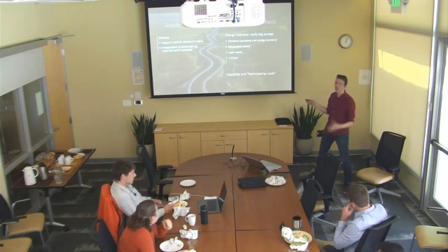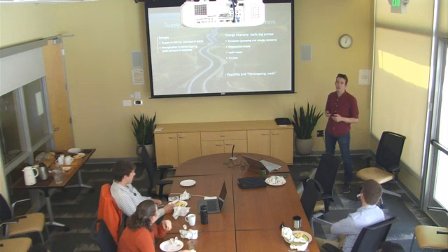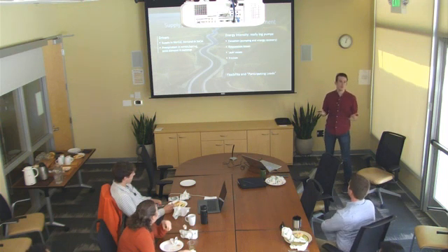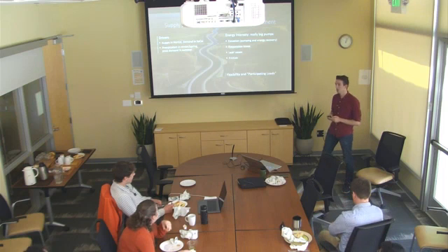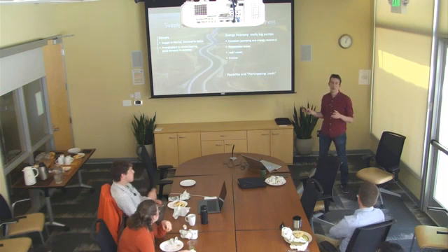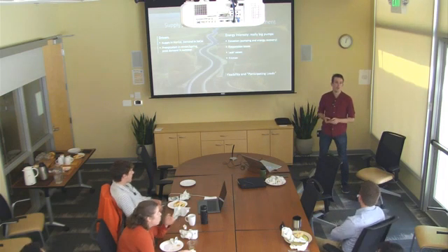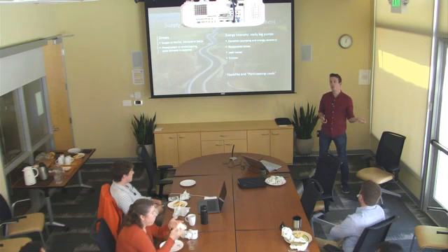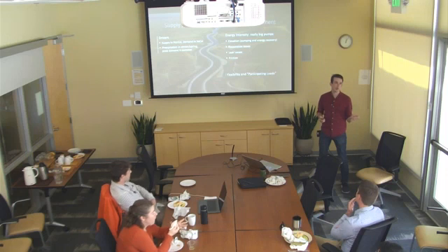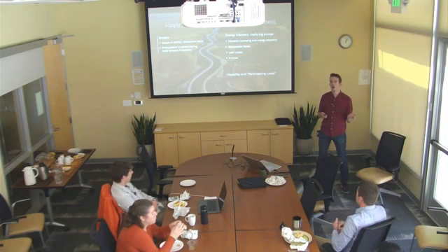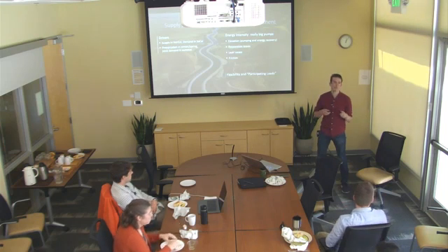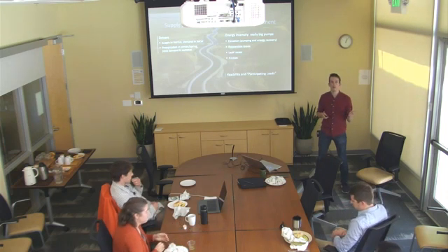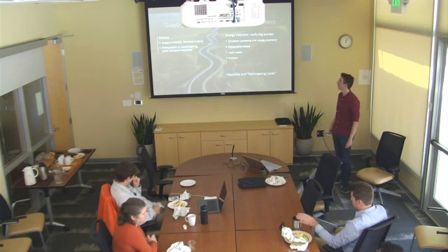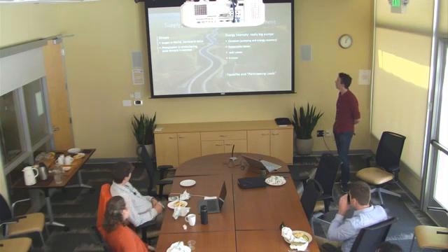One thing about the flexibility of these energy demands is that the pumps that are used in some of these big projects are actually considered participating loads in the wholesale electricity market. So they are one of the few energy load sources that bid directly into CAISO wholesale markets and are thus dispatched almost like a generator, because there's so much storage in the system, it doesn't really depend when exactly they're pumping as long as they're getting that water moved.